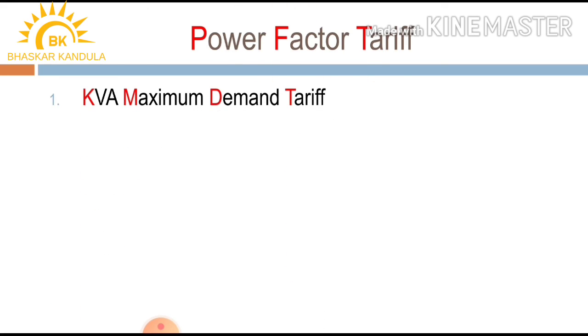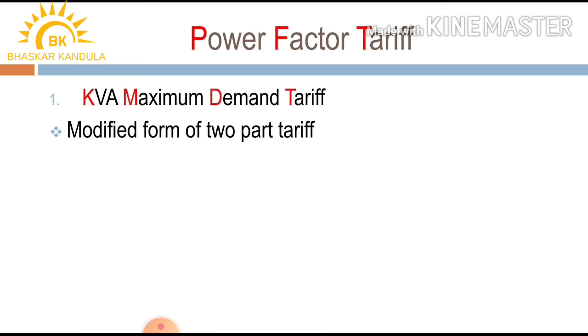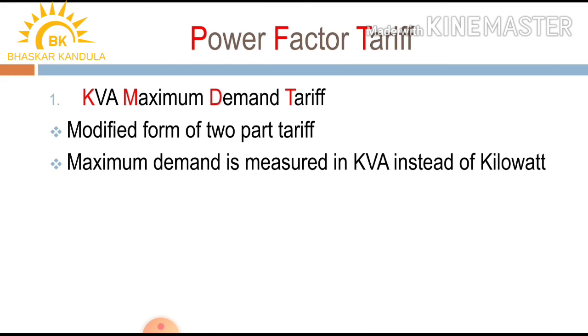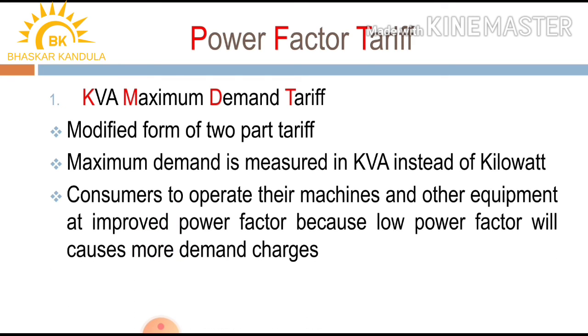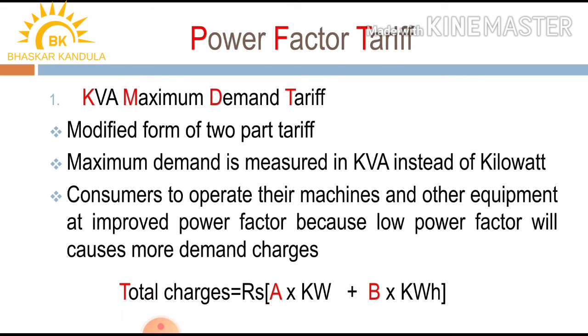The KVA maximum demand tariff is a modified form of two-part tariff. In this case, maximum demand is measured in kilo volt ampere instead of kilowatt. This encourages consumers to operate their machines and equipment at improved power factor, because a lower power factor causes higher demand charges. The expression is: total charges = rupees a × kilowatt + b × kilowatt hour.